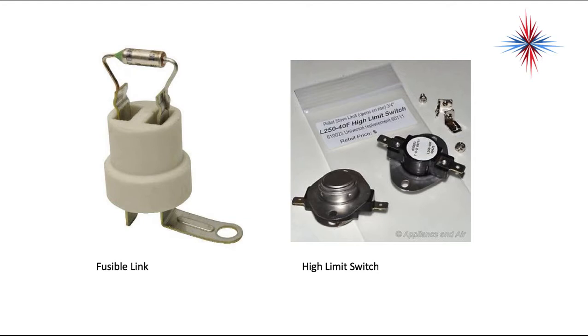So here's some pictures of these two safety devices. On the left-hand side is a fusible link. It's a one-time device. Once it breaks, you have to replace it. The high limit switch is over on the right-hand side. You saw this earlier mounted in the heat strip. Okay? High limit switches will most of the time automatically reset.